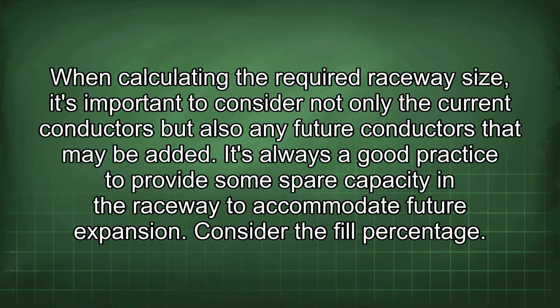When calculating the required raceway size, it's important to consider not only the current conductors but also any future conductors that may be added. It's always a good practice to provide some spare capacity in the raceway to accommodate future expansion. Consider the fill percentage.